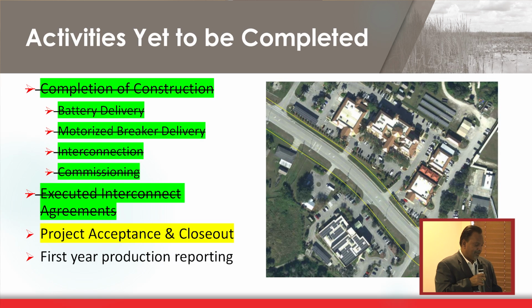But when the project has been completed, then we are going to accept the project and close it out. Because AGT's responsibility is to provide a system that works as it is supposed to work. That is: grid out, battery runs facility, BESS gets depleted after 3 hours or more, then generator kicks in, generator recharges BESS, and generator runs facility. When the BESS gets recharged to 80%, the generator cuts off and the BESS runs the facility for another 3 hours. That is the way the project is supposed to be designed and function. So we have not yet accepted the project or closed it out.